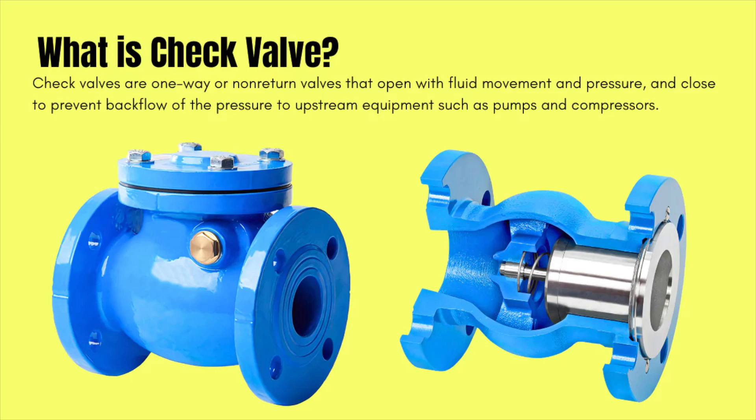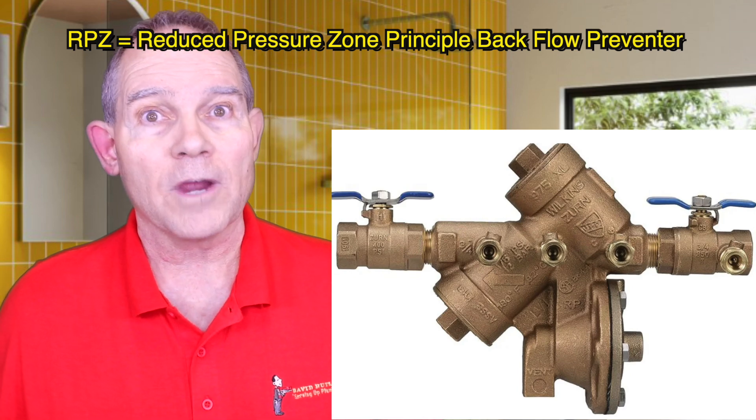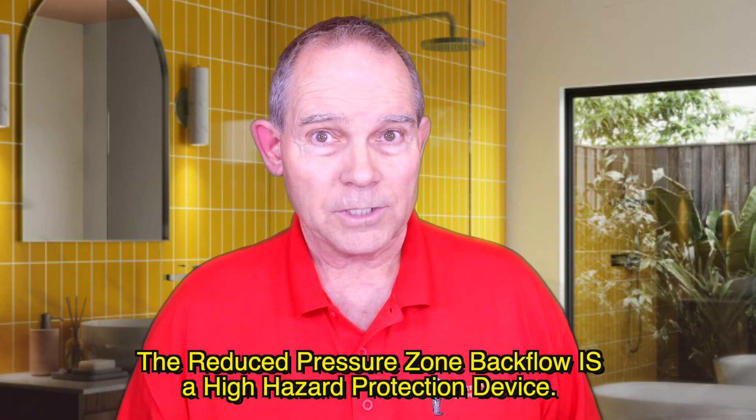Now there are a lot of different backflow preventers: air gaps, pressure vacuum breakers, check valves, the RPZ — which is a reduced pressure zone principle backflow preventer — and the double check. What we're going to be talking about today are the primary ones: the double check assembly and the RPZ valve, the reduced pressure zone principle backflow preventer. The RPZ is the highest level of mechanical backflow protection you can get. The double check is just a level below that — it is not considered a high hazard protection device. So where do we put these and why? Let's talk about it.